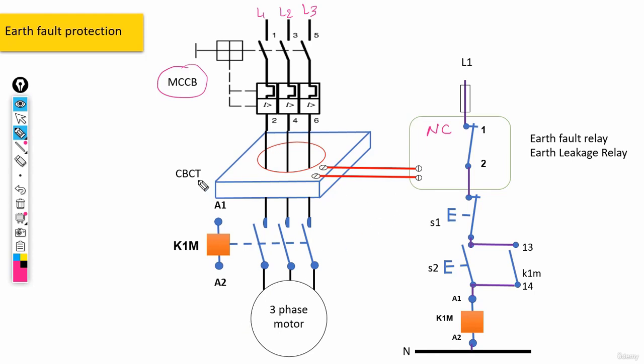Now, let's say the CBCT transformer is giving this signal, and the signal is actually connected to the earth fault relay. And as I said, inside the relay, we have this normally closed contact that is actually set in our control circuit electrical current's path. So as a result, guys, we can simply use this start push button here to activate this contactor.